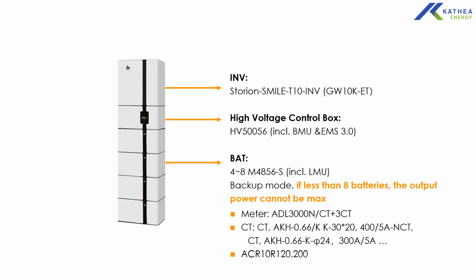But the minimum battery configuration that you can wire to the system is 4 batteries, because the minimum start voltage for the inverter is 180 volts. So definitely you would need 4 batteries as a minimum, and then the maximum you can connect is 8 batteries. So all battery power is in series, wired to the HV box. Your PV array is wired to the HV box. The system offers two strings, 500 and 550 volt VDC, 11 amps. Up to 13 kilowatt of PV can be wired to the system.